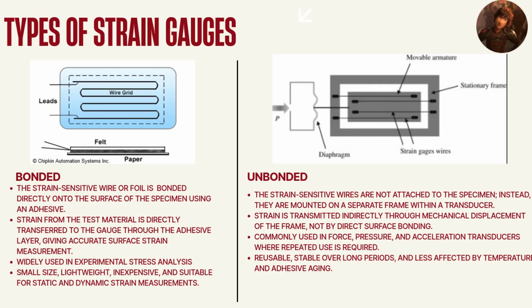In what circumstances are unbonded strain gauges preferred? They are commonly used to measure force, pressure, and acceleration transducer when repeated use is required. So what are the advantages of using unbonded strain gauges? A few advantages are that it is reusable, stable over long periods, and less affected by temperature and adhesive aging.